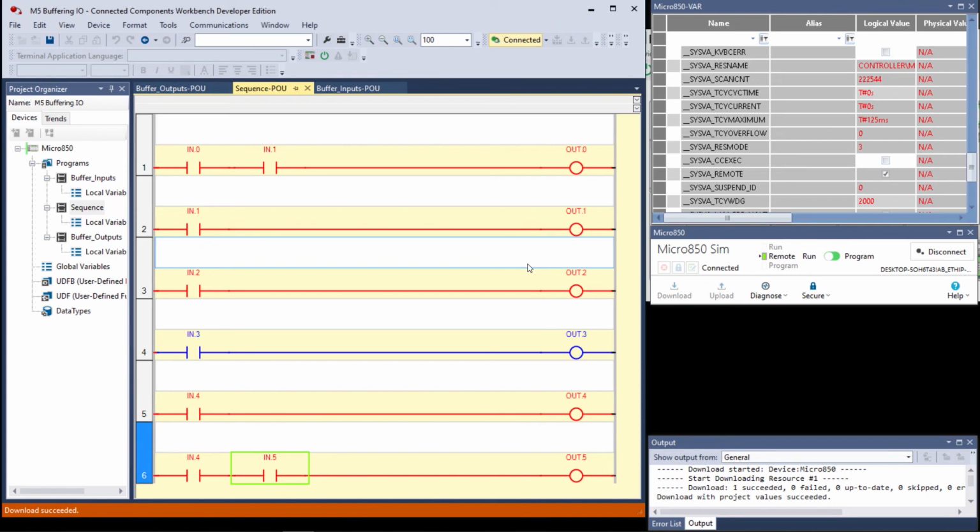Now the way it's actually stated in a true-false sense is input 1.1 is on. That's a true statement, so this instruction is true. So it writes a 1 to output 1. Input dot 3 is on. Well, it's not, therefore this is going to read false and turn off that bit. Because remember, these OTEs or direct coils, they all have a true execution and a false execution. So 5 of these rungs are true. So 5 of these OTEs are executing the true execution. We have 1 that's not. It's executing the false execution.